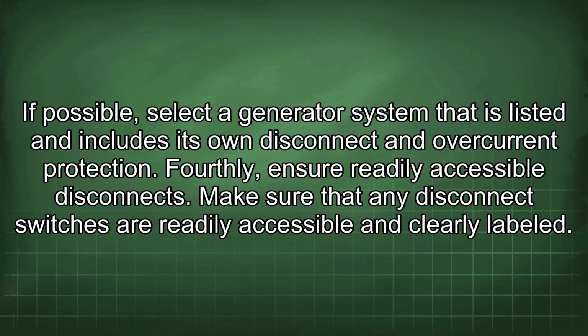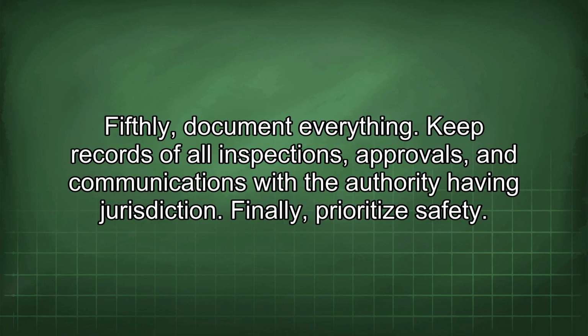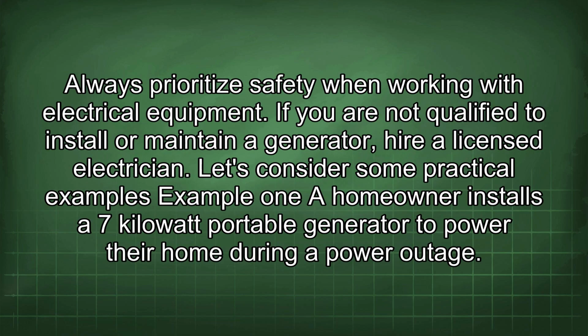If possible, select a generator system that is listed and includes its own disconnect and overcurrent protection. Fourthly, ensure readily accessible disconnects. Make sure that any disconnect switches are readily accessible and clearly labeled. Fifthly, document everything. Keep records of all inspections, approvals, and communications with the authority having jurisdiction. Finally, prioritize safety. Always prioritize safety when working with electrical equipment. If you are not qualified to install or maintain a generator, hire a licensed electrician.